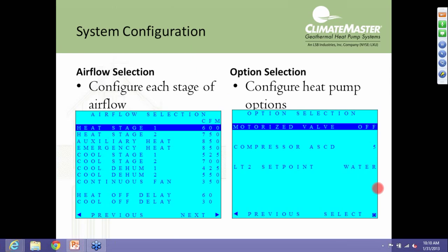Under airflow selection, we can look at the current airflow setting for each mode of operation, heating stage 1, heating stage 2, and so forth. We can select one of those and then adjust the airflow in 25 CFM increments within a min and a max for that particular model. So if I'm configured, let's say, for a TZ036, there will be a min and a max for each one of those categories that I can move the airflow within. Now, if you go into the installation manual for a TZ unit, for instance, you can look at a blower table and it will show the min and the max and then the default. The default will be the factory default setting for that product.